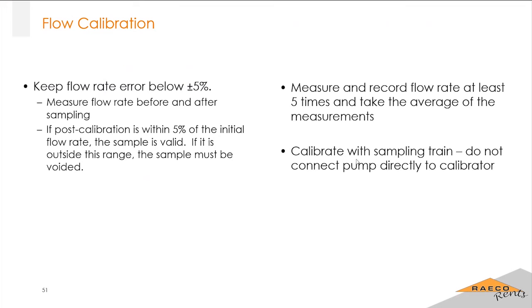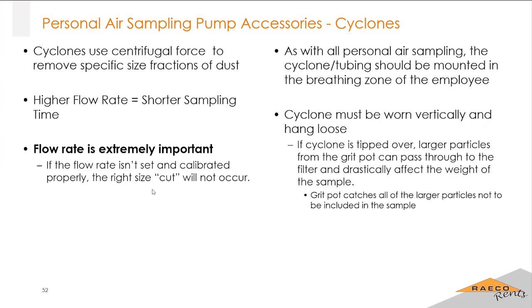And of course, when you do calibrate, do it with your sampling train hooked up. So you don't want to hook up the pump directly to the calibrator and call it a day. You want to mimic exactly what you are sampling. So hook up the pump to the tubing, hook up the tubing to the media, and then hook up the media to the calibrator. That's essentially what we're trying to do with that.